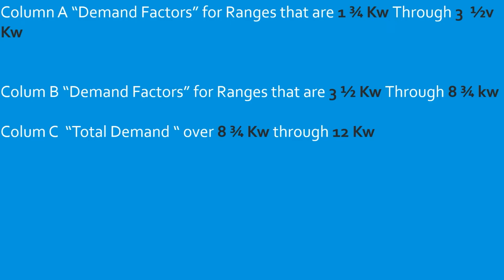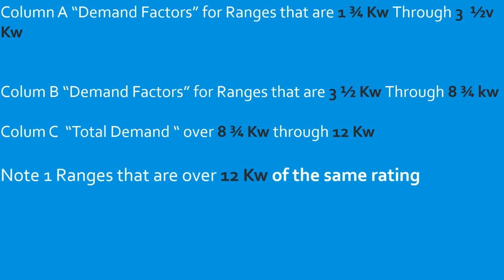If we had two 10 kW ranges, we would go over to the left-hand side and find two appliances, and then we come over and we find out that the new replacement value for both of the ranges is 11 kW. And so on and so forth. Don't worry about having to master all this right away. We're going to work through pretty much every example. Now let's look at the notes.